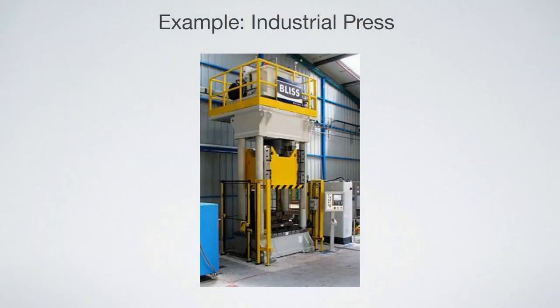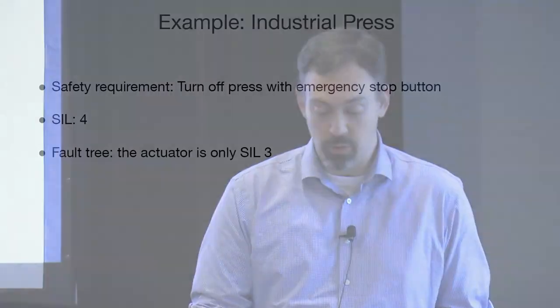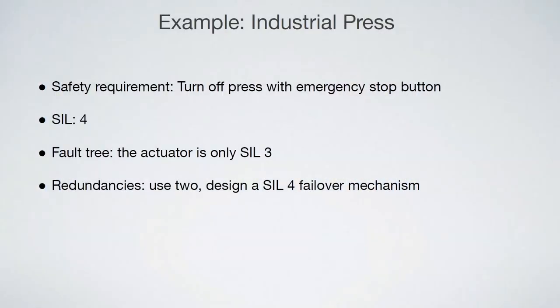A somewhat contrived example: suppose you have a huge industrial press and it's going to have an emergency stop button. Our safety requirement — that thing sure as heck better work. The safety integrity level, on the scale from 1 to 4 used in most standards, with 4 being the most severe — in this case we'll pretend it's 4 because it's definitely going to kill someone. But suppose when you take the system apart, there's the button, the wires going to the actuator, and a little control system. Maybe the actuator's failure rate, based on the supplier's data sheet, only makes it sufficient for safety integrity level 3. Well, we have to add redundancy — we'll use 2 actuators and design a very reliable failover mechanism to meet our requirements for safety integrity level 4.